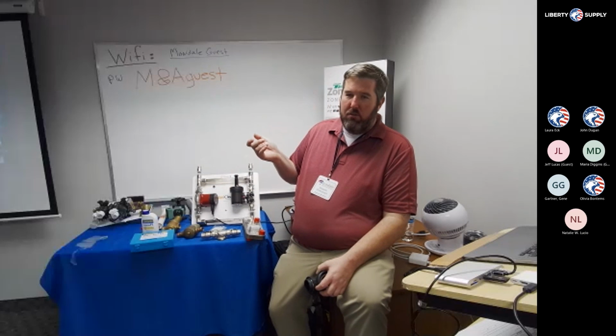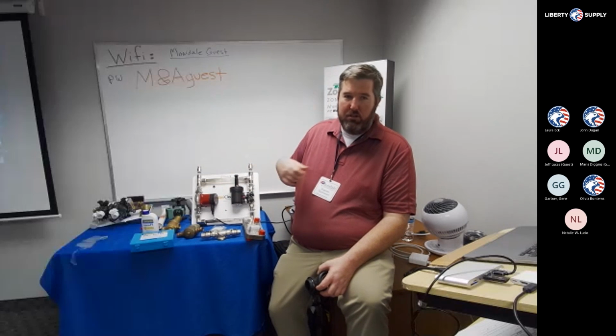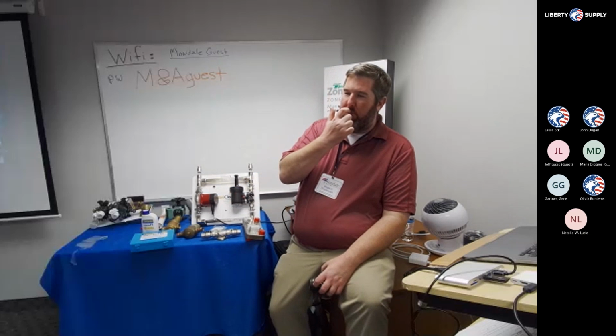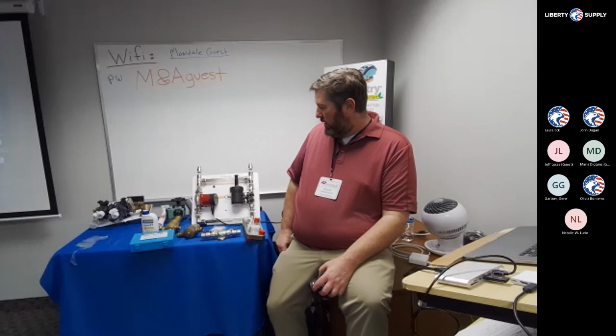If you have a system that doesn't have a lot of iron oxide in the water, you may not need to do a magnetic filter. You may just do a strainer. Some folks have just chosen to do the magnetic filter with the strainer because then you get both benefits. If there is any iron on the system because the cast iron circulator is giving it off, you get that benefit, but you also get the strainer, or in lieu of doing a Y strainer that's hard to take apart and hard to clean, this has been a great benefit for folks that want to do more maintenance and make sure that their system is keeping up with the maintenance on that side. So those are all items for us to kind of deal with.